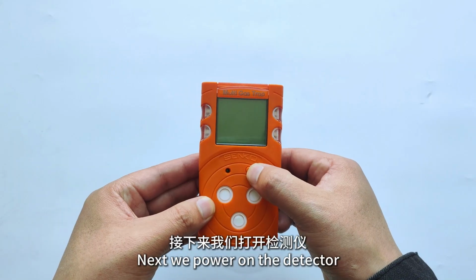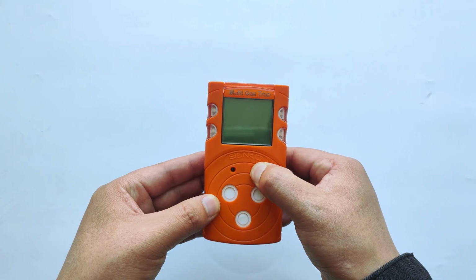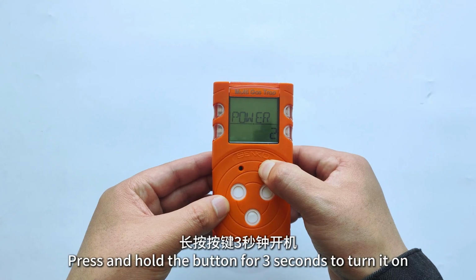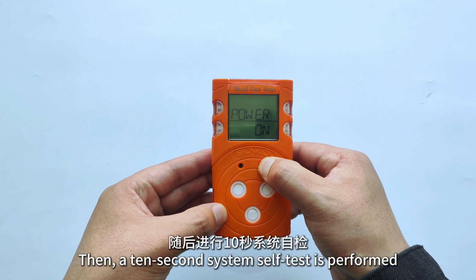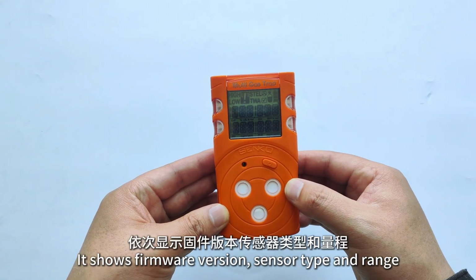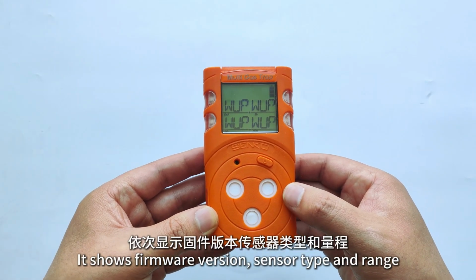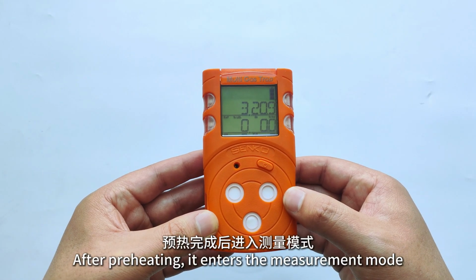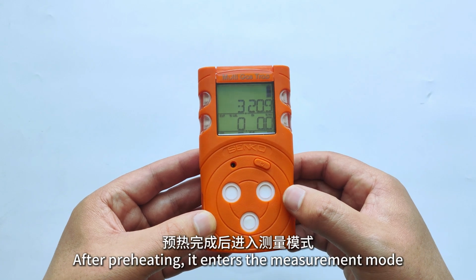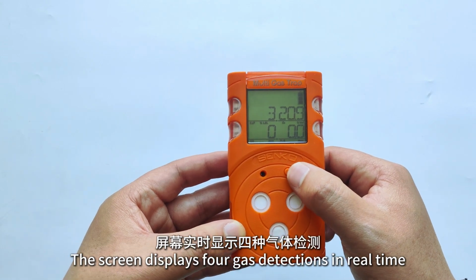Next, we power on the detector. Press and hold the button for 3 seconds to turn it on. Then, a 10-second system self-test is performed. It shows firmware version, sensor type, and range. After preheating, it enters the measurement mode. The screen displays four gas detections in real time.